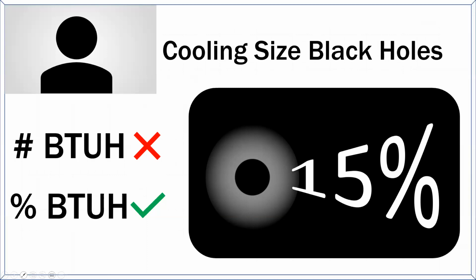And it's because of what I like to call the black holes. The number of BTUs is not what I'm worried about, it's the percentage. I don't care if you're 2,000 BTUs over or 10,000 BTUs over—if 2,000 BTUs is half the load on a mini split, that's terrible.